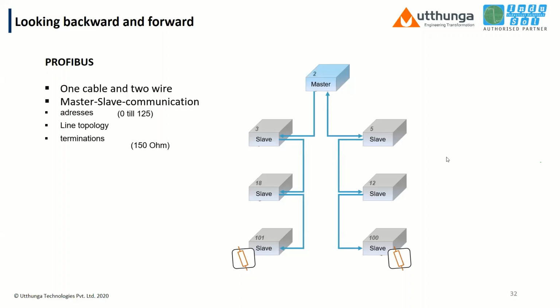Like if energy is flowing from here, you can see 150 ohms. It will not get reflected if the resistance is here, like it will be grounded properly. That's why we ask to terminate at the start of the segment and the end of the segment. Measurement points: with PBQ1, the signal quality tester, you have to measure at these particular points.